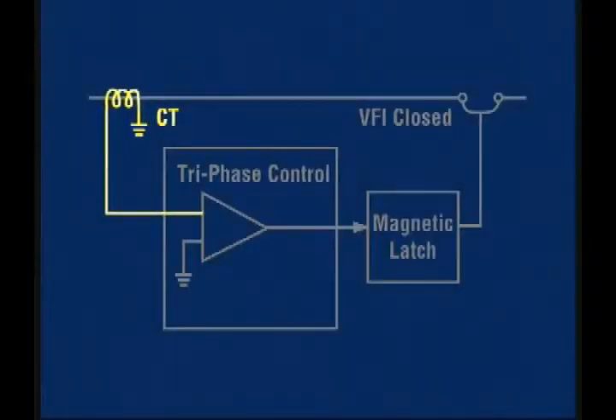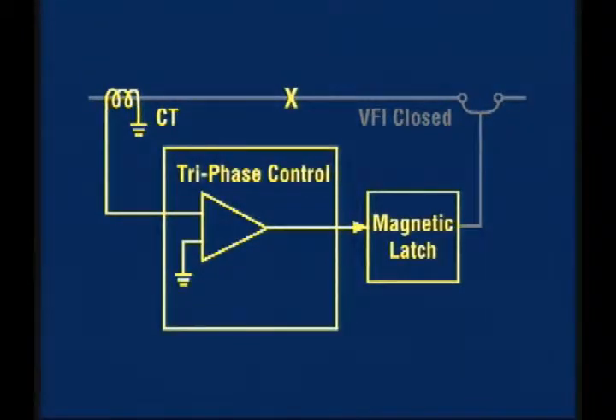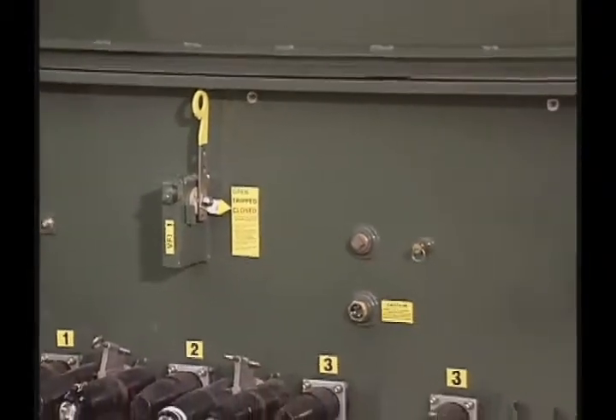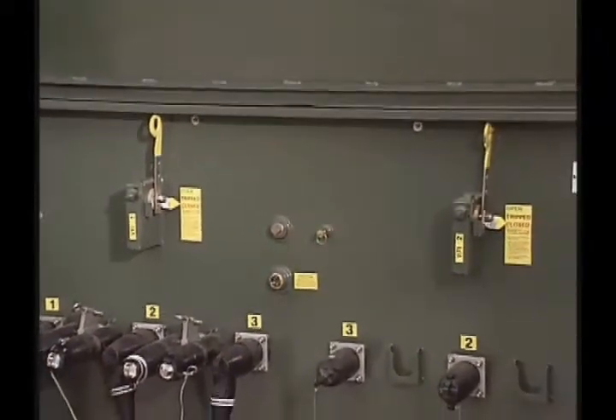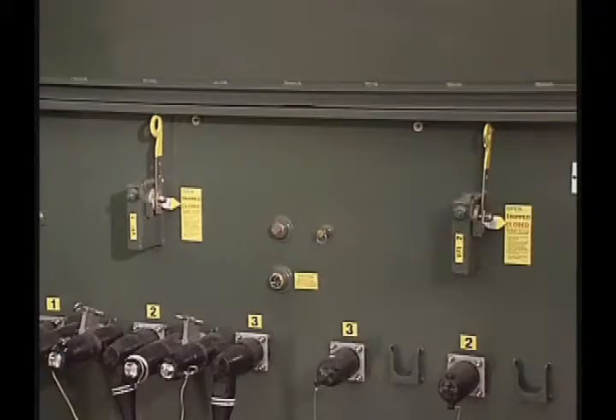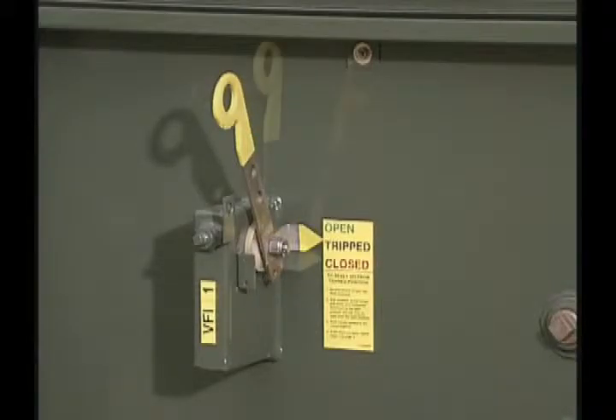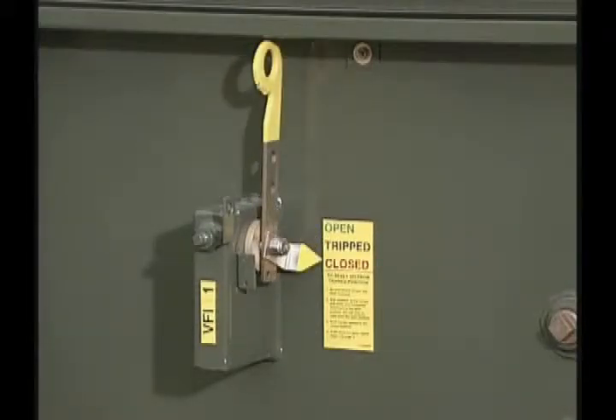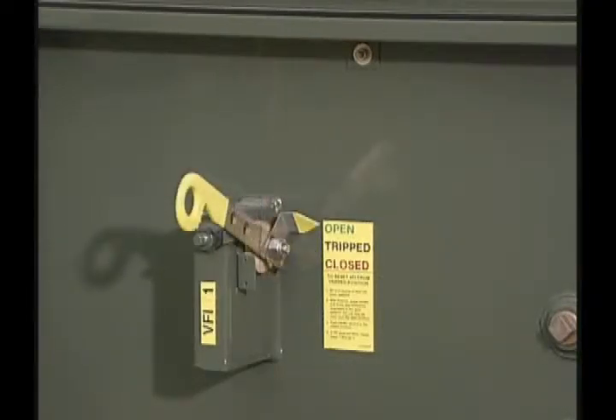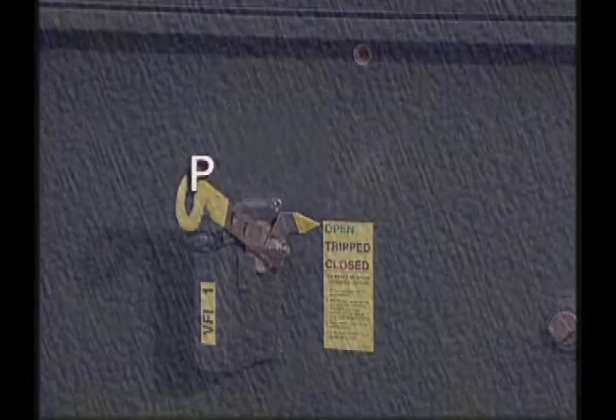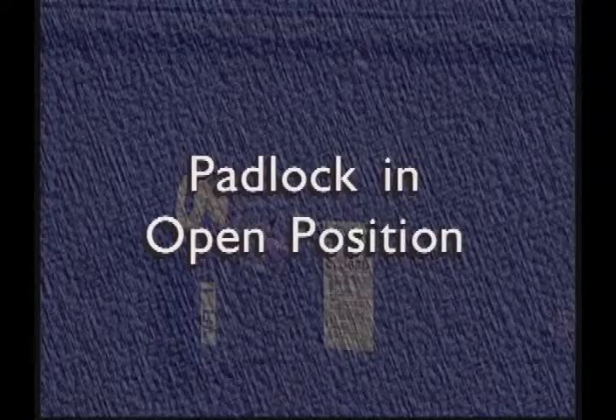Current sensing transformers, or CTs, provide line current information to the control. When the line current exceeds the minimum trip setting, the control initiates a signal, which causes the VFI to interrupt the circuit. The VFI mechanism is equipped with hot stick operable handles that are typically mounted on the tap side of the unit. The operating handles provide push to close, pull to open, and pull to reset operation. They can be padlocked in the open position.